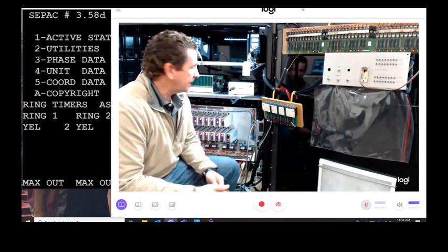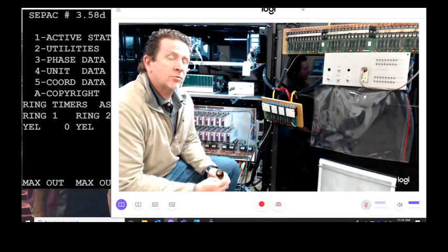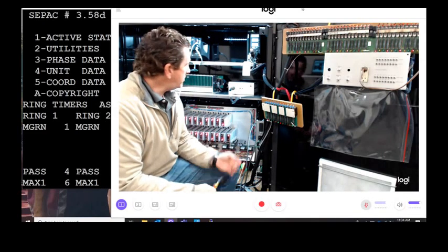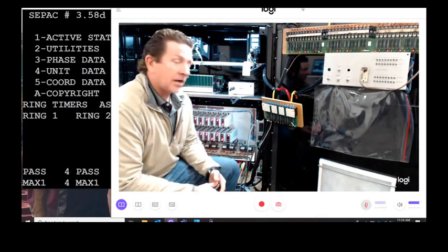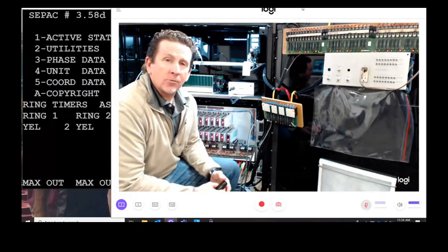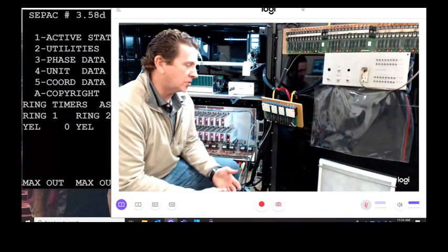The other voltage in there is 12 volts AC. 12 volts AC has one purpose in the TS2 cabinet. That's your PED circuit. When I lose that, or I blow that fuse out, I lose my PED circuit. So people are like, hey, my PED's not working anymore. My input is dead. And they start troubleshooting all sorts of other things.